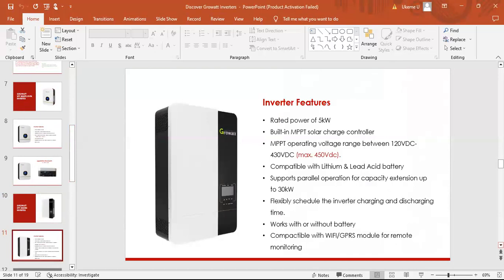So I was explaining the flexibility in scheduling the inverter charging and discharging time. So this particular one has the ability to schedule the charging time and the discharge time for the battery. The first feature I stated is that this works with or without battery. You can decide to run it without a battery system. The only time you'll be needing a battery system for this one is maybe in the case you will need a backup system at night when there will be no sunlight or the grid supply. But if you must use this particular one with no battery, you must make sure that the load that will be put on this inverter should be less than what your solar panels, your PV array, can produce. Otherwise, the system will not work.